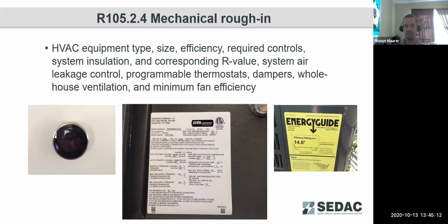If you've got an ERV system or a supply side fresh air system, that the dampers that are connected to those systems are installed properly and working properly. And if you've got a whole house ventilation fan, that fan meets minimum fan efficiency requirements.